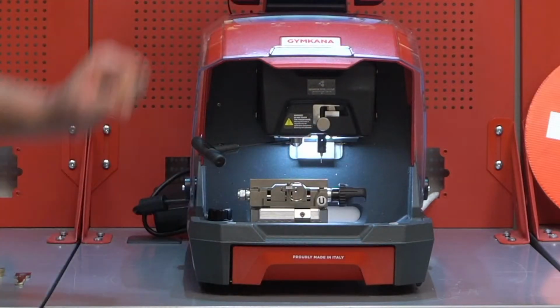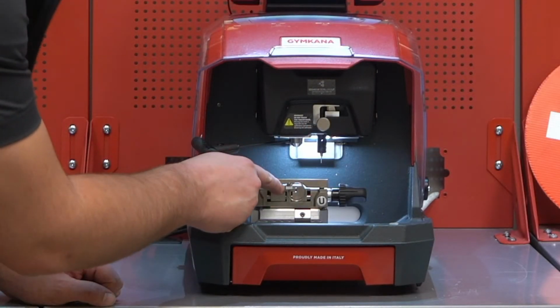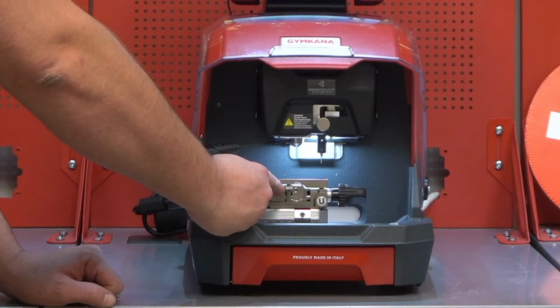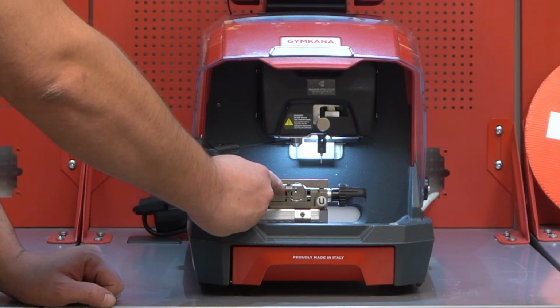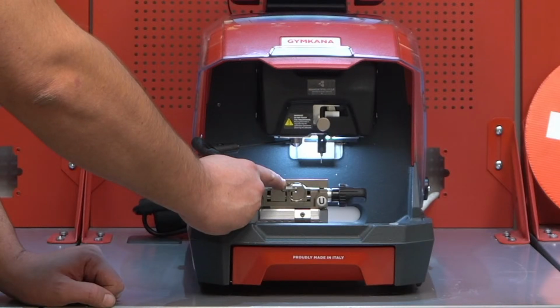And then you tighten down the calibration template. When you tighten it down, it should automatically center it in the U-jaw, so you don't even have to worry about that. You just push it in until it hits the stoppers, and then you're good to go.